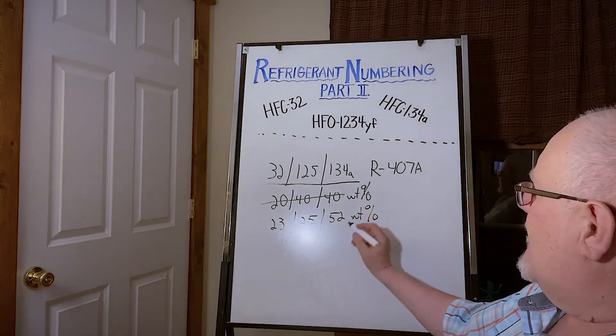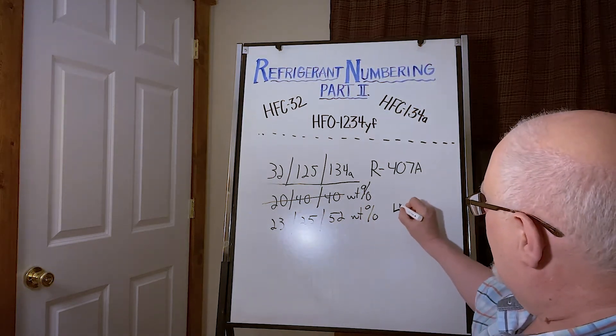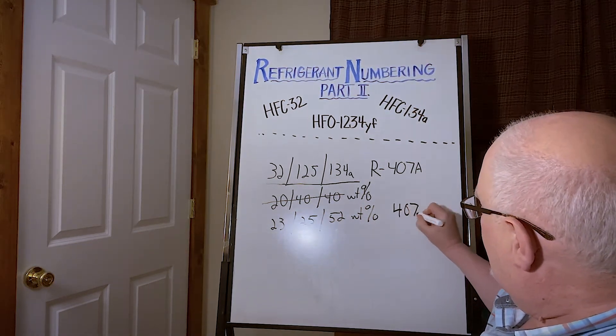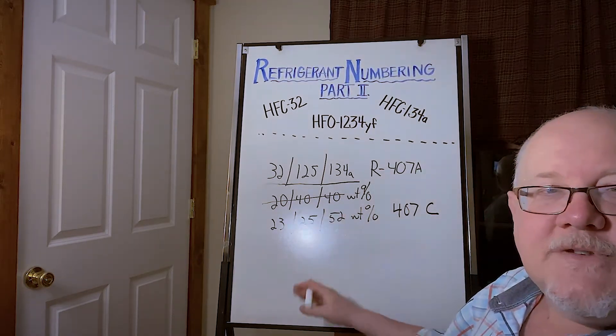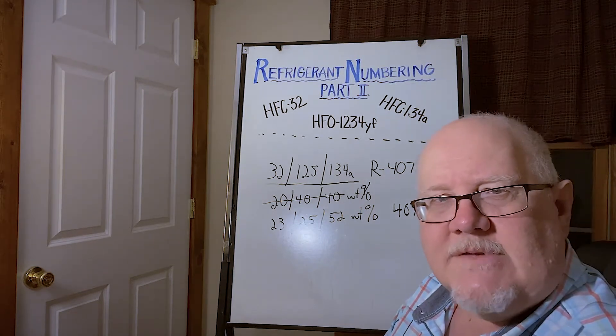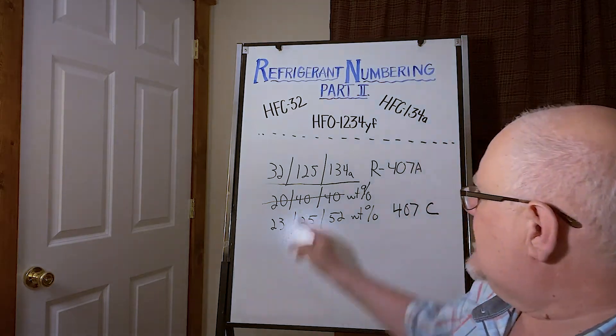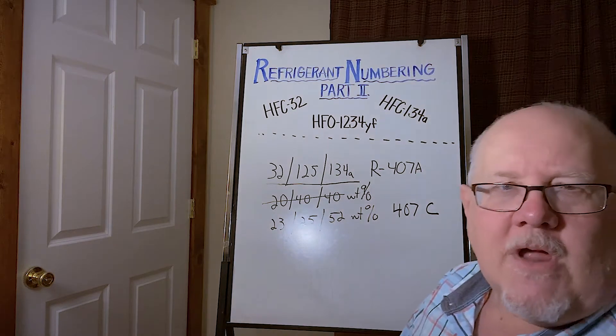But this 23, 25, 52 weight percent was given a 407C designation. And then there's D, E, F, G, H, ongoing. I'm not sure how high the 407 series is now, but every time it's the same three components, different combination.